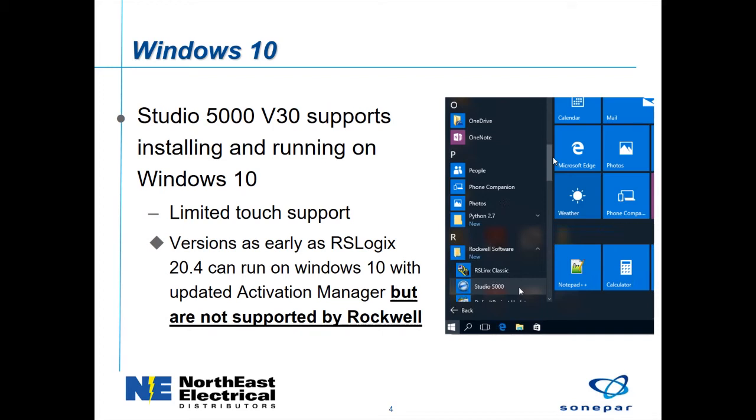One side note, I have seen versions prior to Studio 5000, or really RSLogix 5000 version 20.4, run on Windows 10. In general, what you have to do is update Activation Manager. But this is a configuration that is not supported by Rockwell. You cannot call in for help with installation or programming issues if you have something prior to version 30 running on Windows 10.